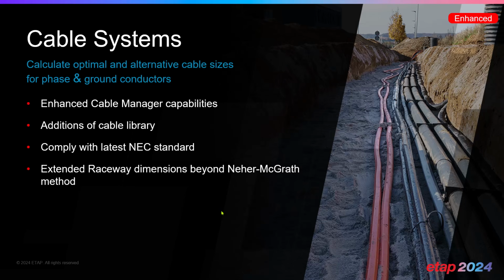And finally, the cables, when we are performing thermal analysis, are typically done in an underground raceway system that ETAP provides as a module. And one of the methods in there is the Neher-McGrath method, which has certain dimension limitations. We've overcome those raceway dimension limitations by creating a new extended method that allows for larger raceways beyond what was allowed in the Neher-McGrath method. So in other words, you can build larger raceways, larger dimensions with the latest compliance in terms of cables, and visualize not only your cable size, but also the thermal temperature of the conductors.